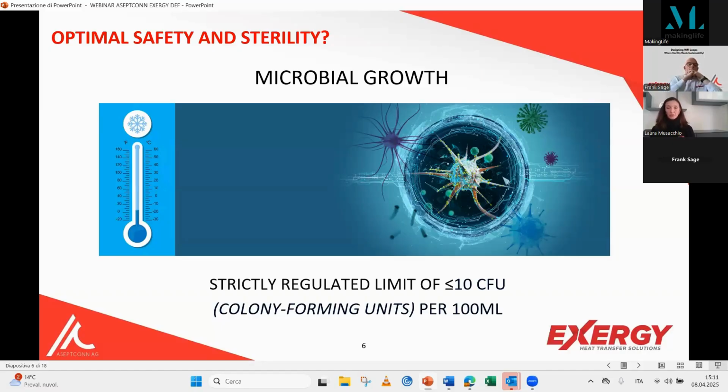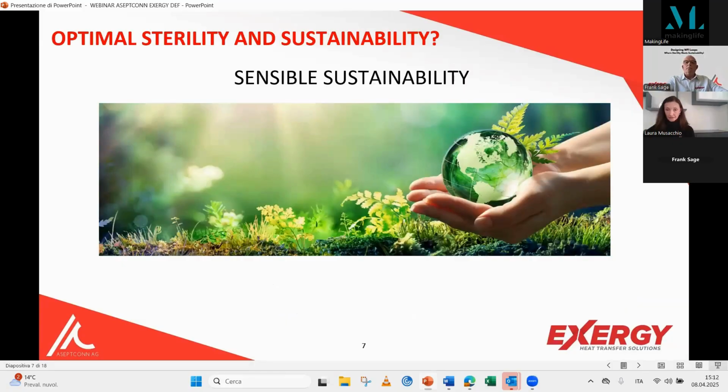In fact, when the thermal WFI is cooled to ambient temperature in the distribution loops, we need a lot of monitoring at the dispensing, instrumentation, and sterilization sides. When we sterilize and optimize this typology of monitoring, in terms of manufacture, we have a high risk of having to stop all the process for downtime, considering that we could have 12 hours of hot WFI sterilization every 2 days, more or less.